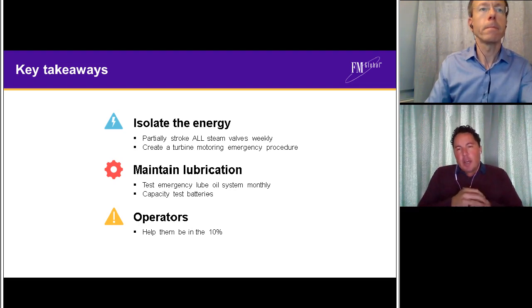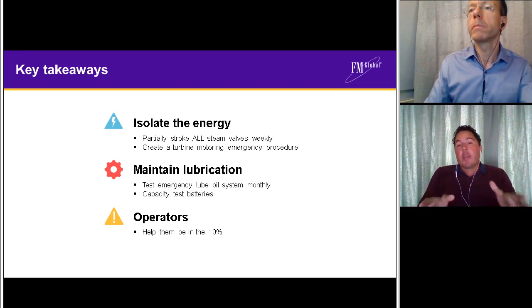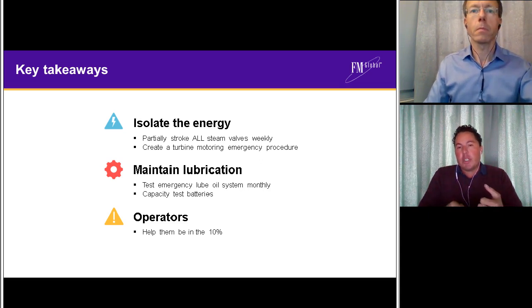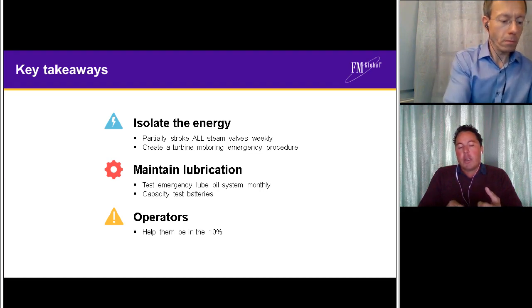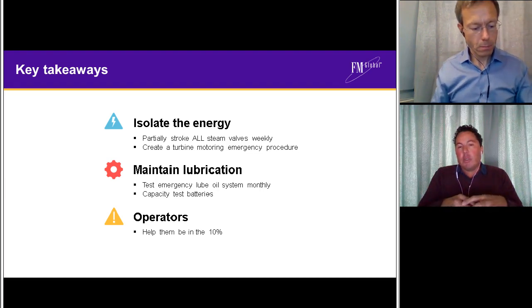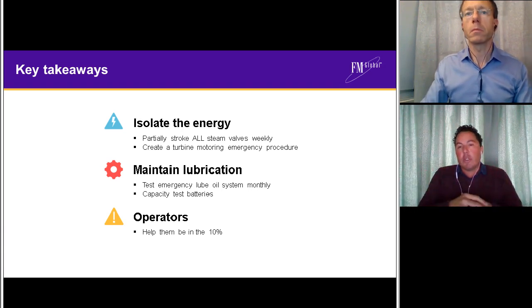Again, great question. I think to clarify, the recommendation is on valve-regulated lead-acid batteries, and I apologize if I wasn't specific about that in the presentation. The drive here is that flooded lead acids are well known, they're pretty robust, their limitations are well appreciated. Valve-regulated lead acid batteries, which have seen an absolute explosion in their use over the last 5 to 10 years, I think their limitations and idiosyncrasies are slightly less well appreciated, although becoming more and more well appreciated as time goes on.